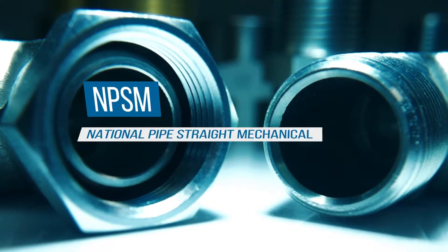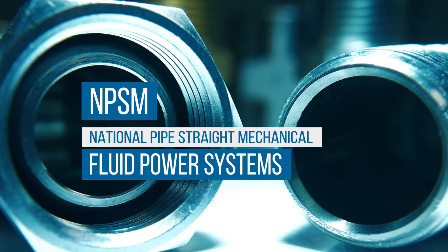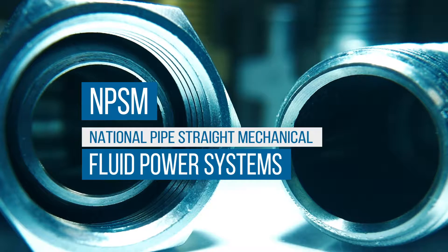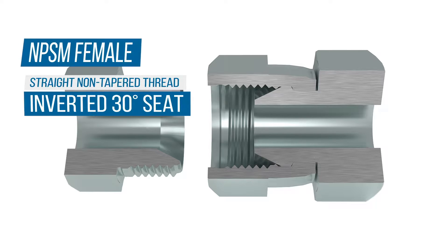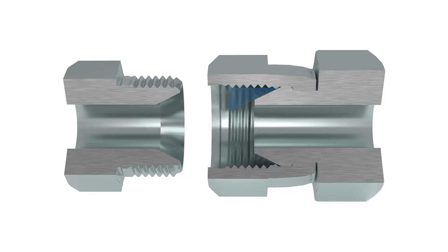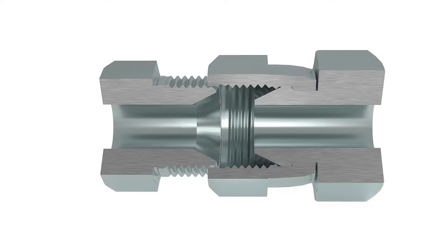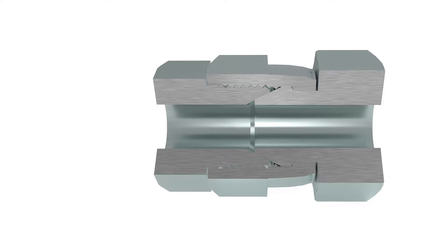NPSM, or National Pipe Straight Mechanical threads, are also often found in fluid power systems. The female component incorporates a straight, non-tapered thread with an inverted 30-degree seat. A seal is made by compression of the 30-degree chamfer of the male connector on the seat of the female. This is a mechanical seal.